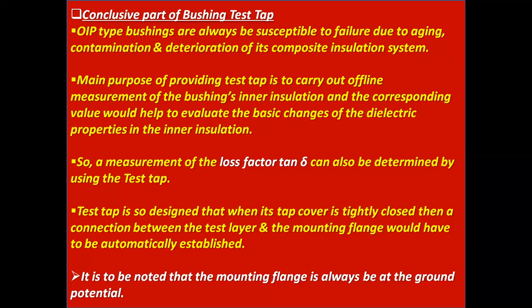The test tap is designed so that when its tap cover is tightly closed, a connection between the test layer and the mounting flange is automatically established. It is to be noted that the mounting flange is always at ground potential.